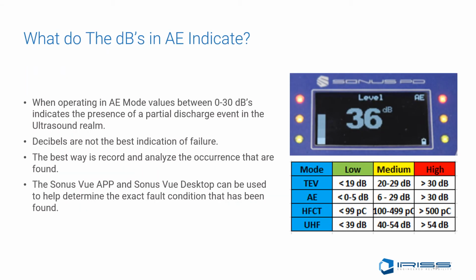What do the decibels in the AE mode indicate? When operating in AE mode, values between 0 to 30 decibels indicate the presence of a partial discharge event in the ultrasound realm. Decibels, however, are not the best indication of failure. The best way is to record and analyze the occurrences that are found. The Sonus Vue app and Sonus Vue desktop can be used to determine the exact fault condition that has been found in electrical gear.